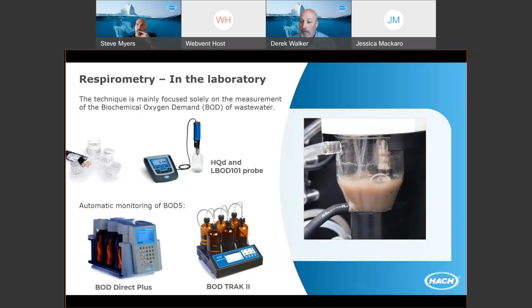On the next slide, you'll see how this technology can actually be brought into the process. So a grab sample of sludge no longer needs to be taken back to the laboratory, but it can actually be sampled directly from the influent streams as well as the aeration basins and measured using a process analyzer. This process analyzer is a Hach unit, and it's called the EZ7900 influent toxicity analyzer. And this actually enables facilities and operators to measure real activated sludge without grab samples and doing a continuous measurement where a data point of a toxicity index is gathered every 15 minutes.